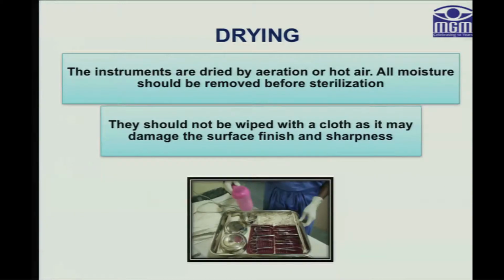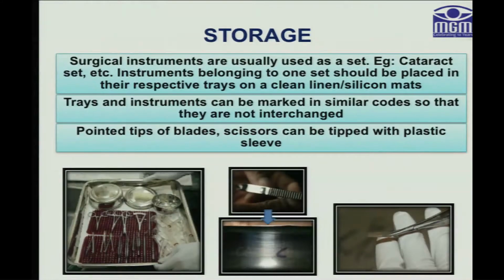The instruments are dried by aeration or hot air, because all moisture should be removed before we go for the next step of sterilization, and we should never wipe them with a cloth. Following this, the storage part comes, where the surgical instruments are usually used as a set, like a cataract set or glaucoma set, and so instruments belonging to a particular set should be placed in the respective trays on a clean linen or silicone mats. Trays and instruments should be marked in similar codes so that they are not interchanged.